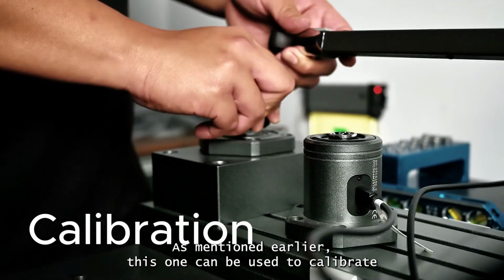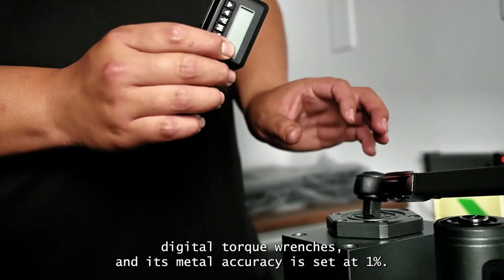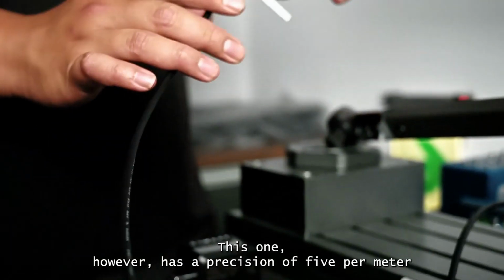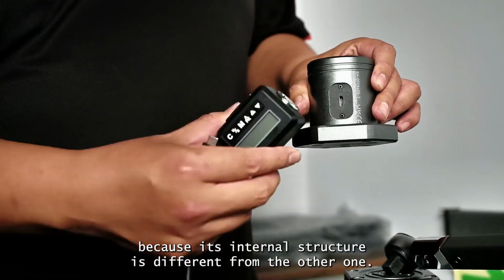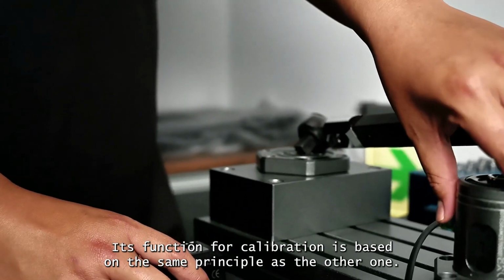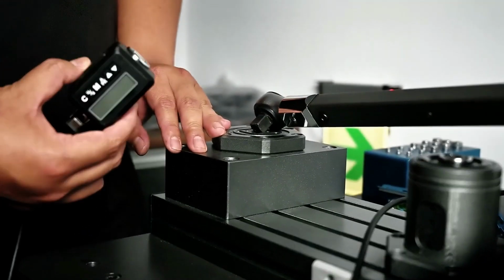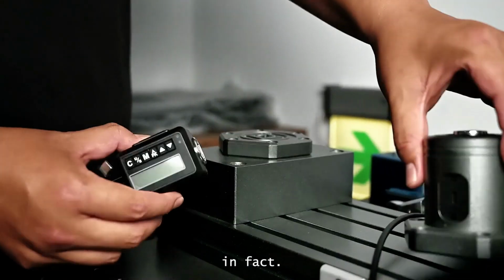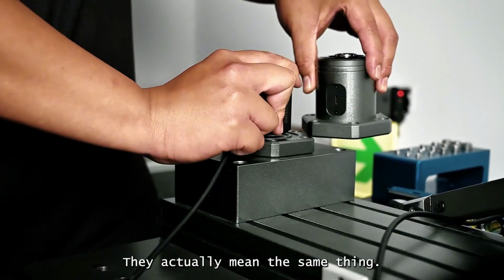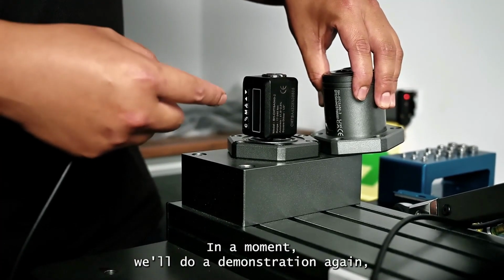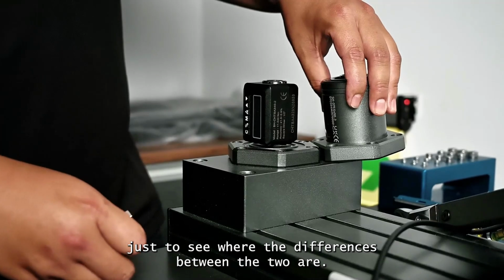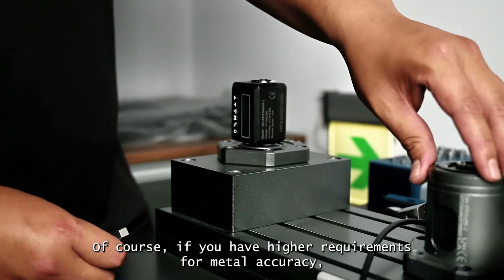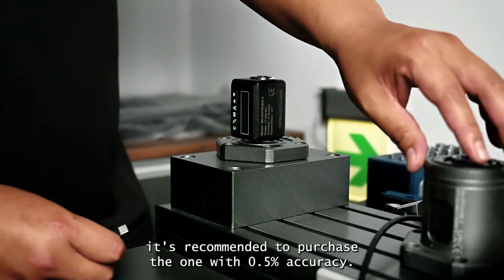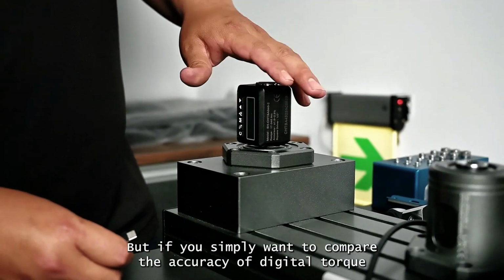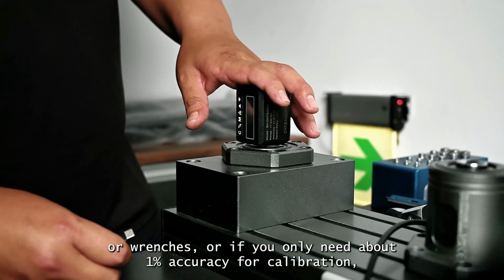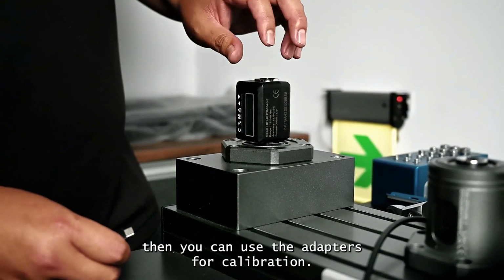As mentioned earlier, this one can be used to calibrate digital torque wrenches, and its accuracy is set at 1%. This one, however, has a precision of 5 per mille because its internal structure is different from the other one. Its function for calibration is based on the same principle as the other one. You can see that the two of them, in fact, they actually mean the same thing. In a moment, we'll do a demonstration again, just to see where the differences between the two are. Of course, if you have higher requirements for accuracy, it's recommended to purchase the one with 0.5% accuracy. But if you simply want to compare the accuracy of digital torque wrenches, or if you only need about 1% accuracy for calibration, then you can use the adapters for calibration.